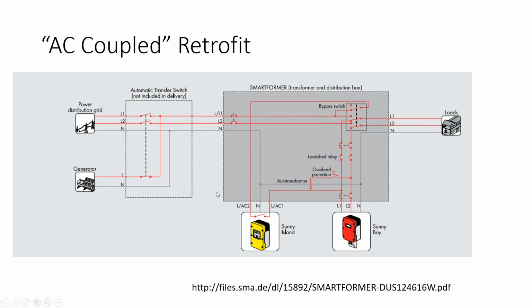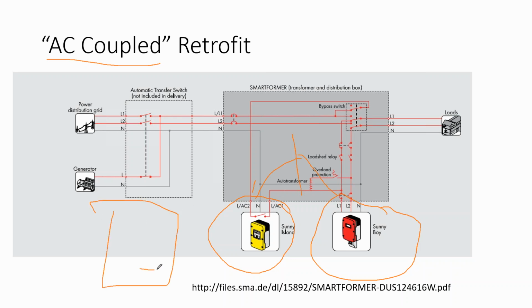All right, let's put that on the shelf for a minute and talk about some system designs, system configurations. One popular debate in battery systems is, are you going to do what's called an AC coupled system versus a DC coupled system? Now, an AC coupled system is where you have a solar inverter and you have a battery inverter, and they're plugged into the same electric service panel. And so you might have your electric service panel with a breaker slot, and you put in your solar array here, and you put in your battery array there.